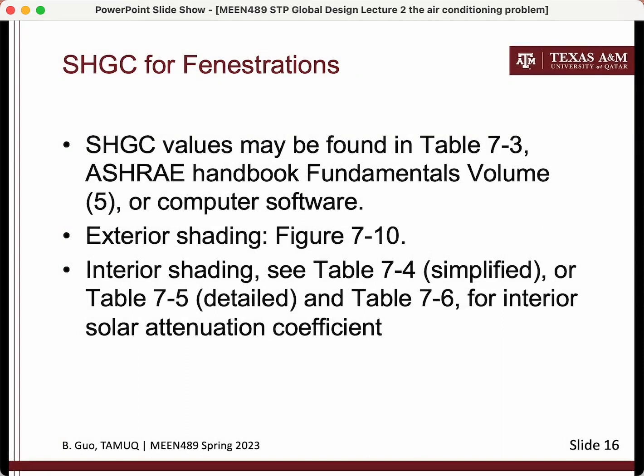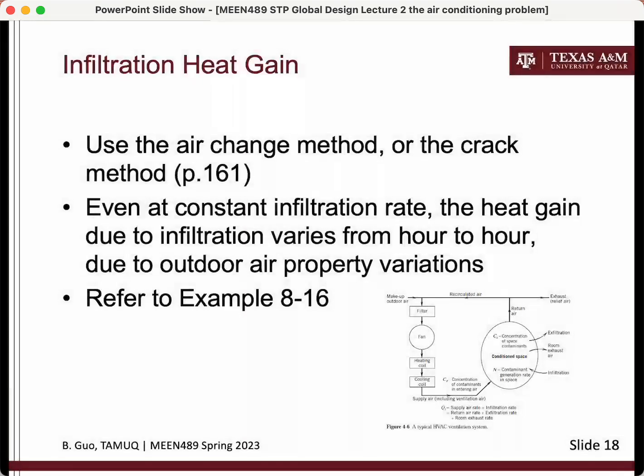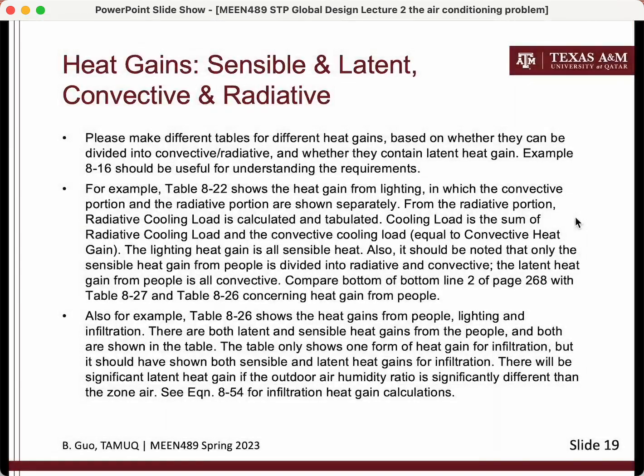Information about obtaining the solar heat gain coefficient (SHGC) for windows and skylights is also covered. Internal heat gains are calculated based on what is present in the indoor environment — occupants, lighting, and other equipment. Infiltration heat gain depends on how leaky the building is and how often doors are opened and closed. Each heat gain must be classified along two dimensions: whether it is sensible or latent, and whether it is convective or radiative.